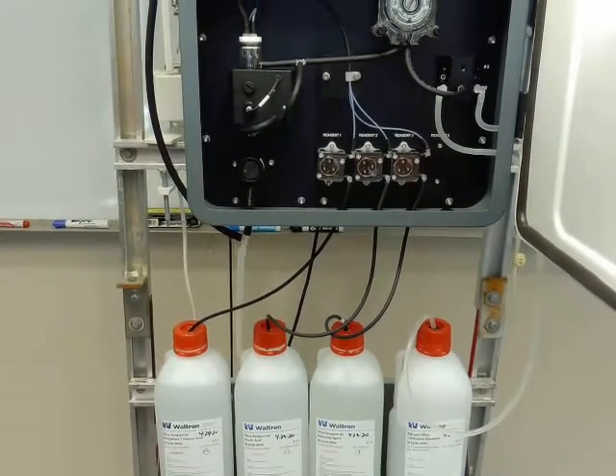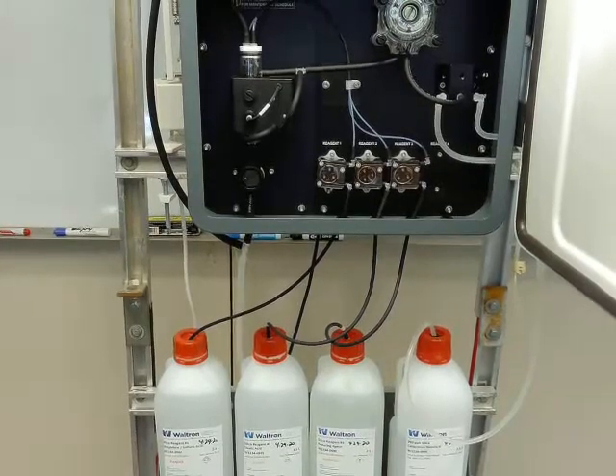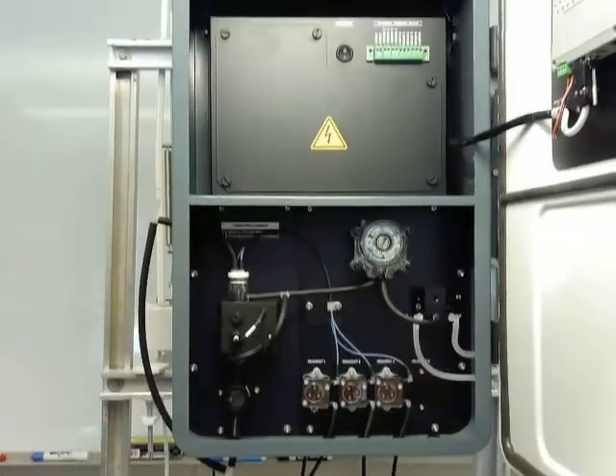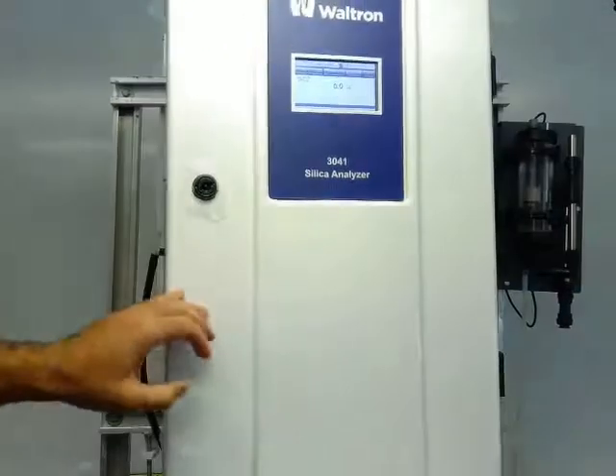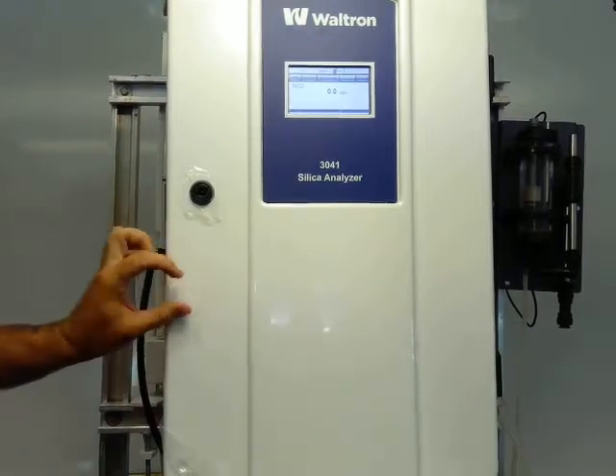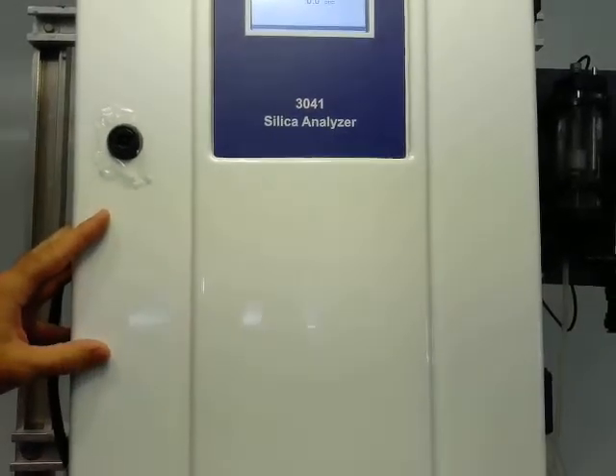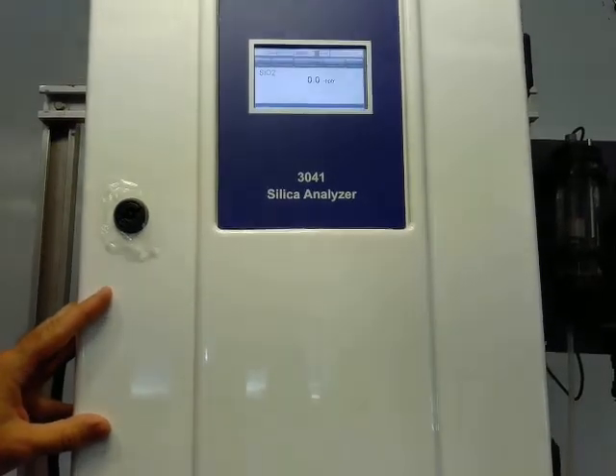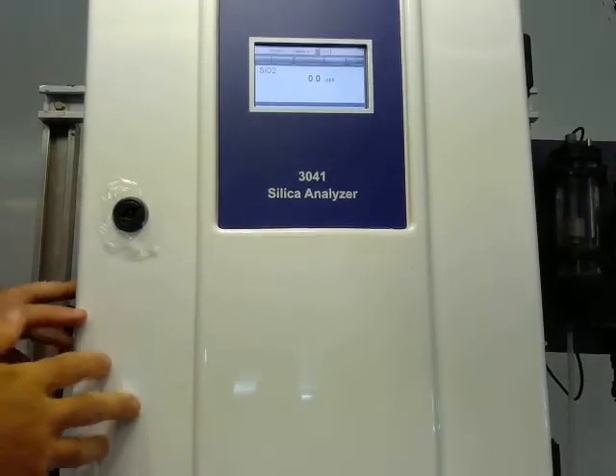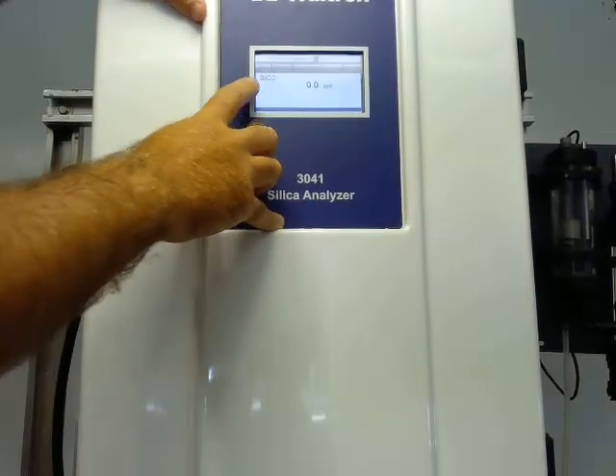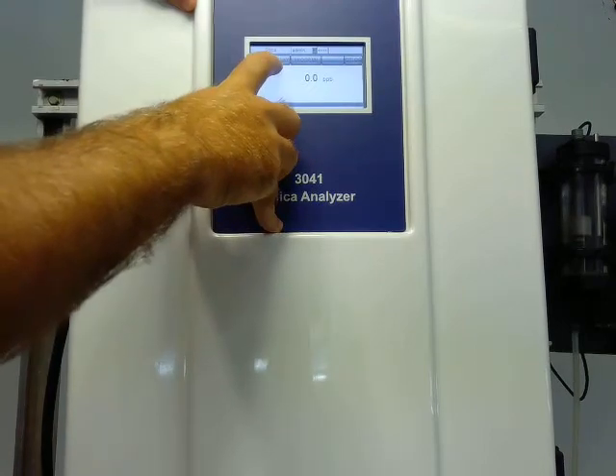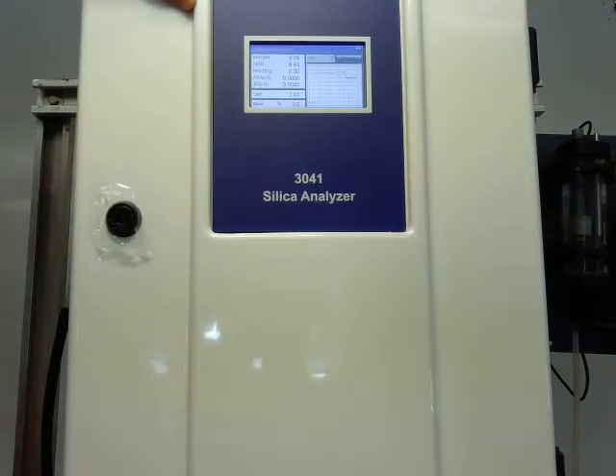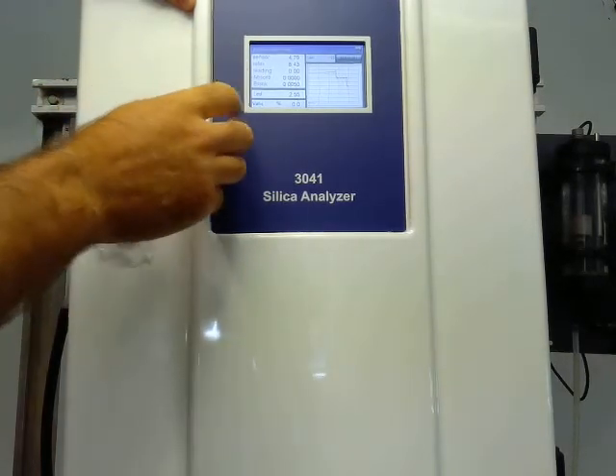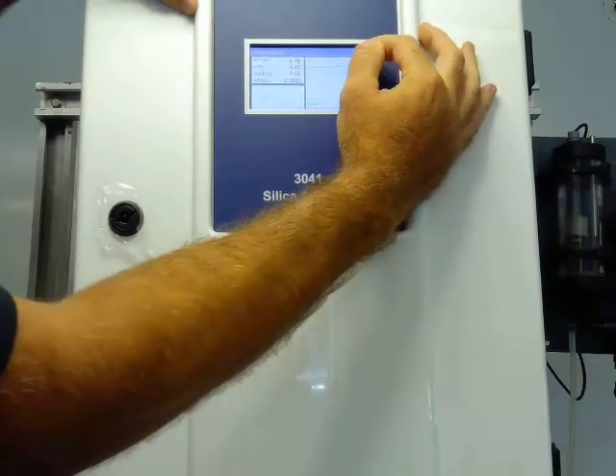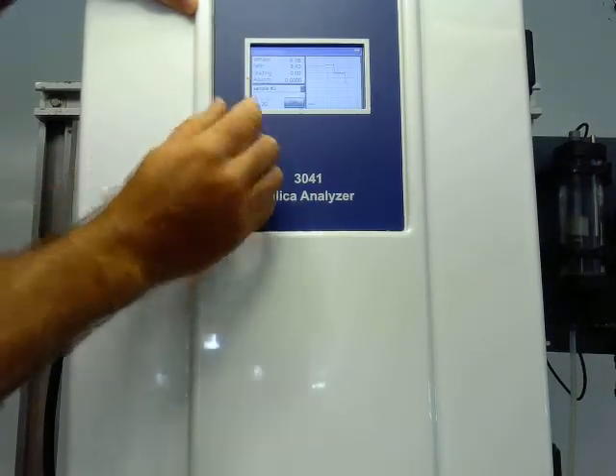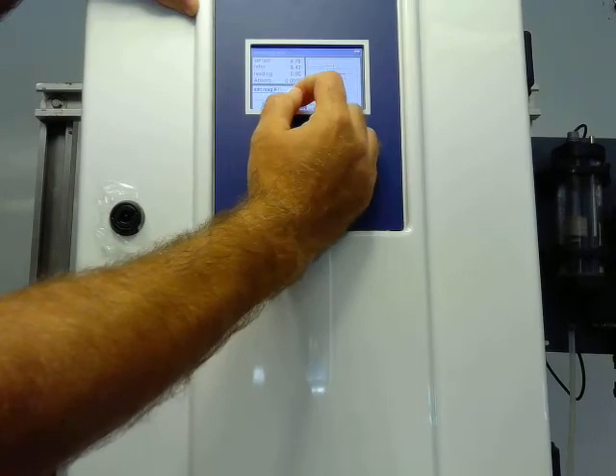So once we have the reagents and tubing installed, we'll want to prime our reagents. If we look at our screen, our second option is this display button. Once we press display, we get a lot of numbers: our sensor value, our reference, our reading. But what we're looking for is this manual commands button over here on the right. That's going to bring up this drop-down menu, and we'll scroll down and look for add reagent 1.